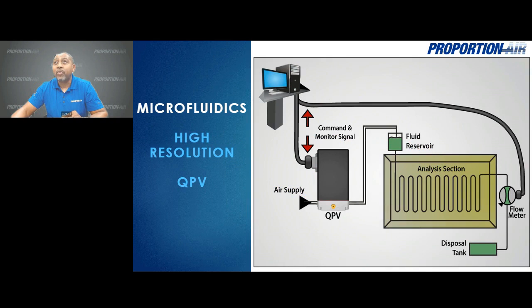A very common use for high resolution products is microfluidic applications, where very small amounts of a gas or a liquid must move through tiny channels. When you use highly accurate and high resolution products, it provides stable and repeatable pressure control, which results in stable and repeatable flow through the microfluidic channel. Our MPV and QPV electronic pressure regulators can be used to precisely control the pressure to a single microfluidic channel or multiple channels. These products offer accuracy of plus or minus 0.2% and a resolution of up to plus or minus 0.005% of full-scale calibration. Again, that stable and repeatable pressure control results in stable and repeatable flow through the channel.